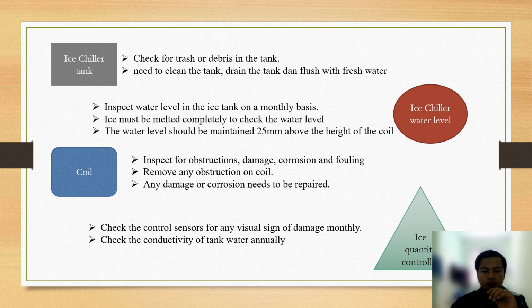For the coil, inspect for obstruction, damage, corrosion and fouling. After that, remove any obstruction on the coil. And lastly, any damage or corrosion needs to be repaired. For the ice quantity controller, check the control sensor for any visual sign of damage monthly. And lastly, check the conductivity of the tank water annually.